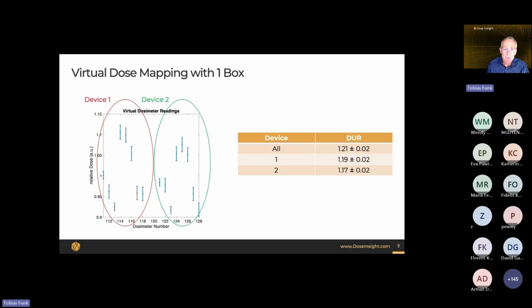So here, we obviously can go to quantitative analysis by reading out the quantitative numbers of the dosimeters, and this is shown for device 1 and 2, and we get an overall dose uniformity ratio of 1.21, which is pretty good. But now we want to see how many of these boxes can we really irradiate before our dose uniformity ratio goes bad.